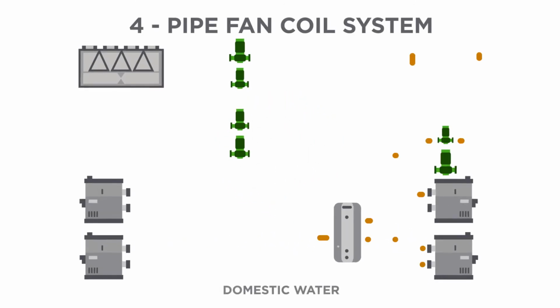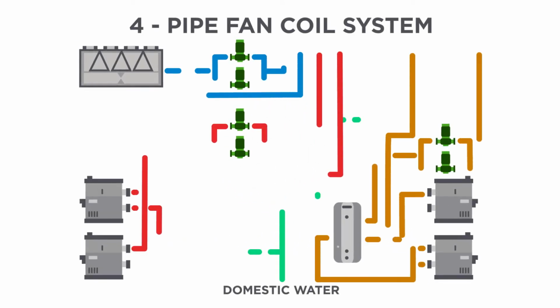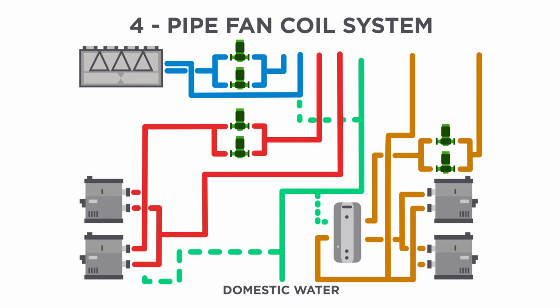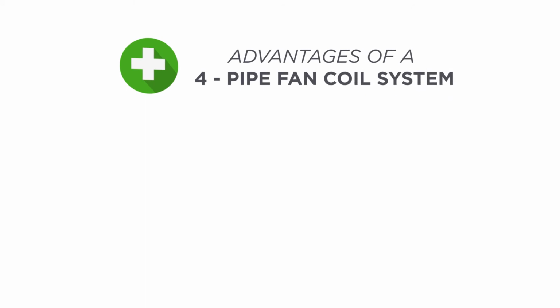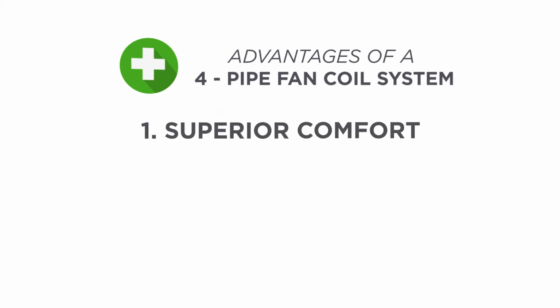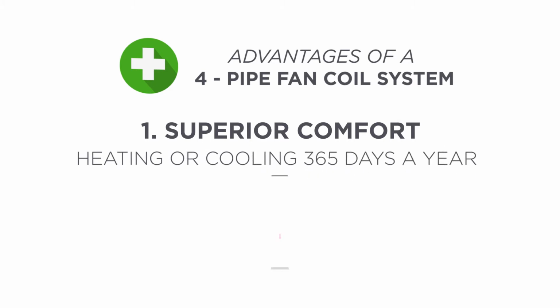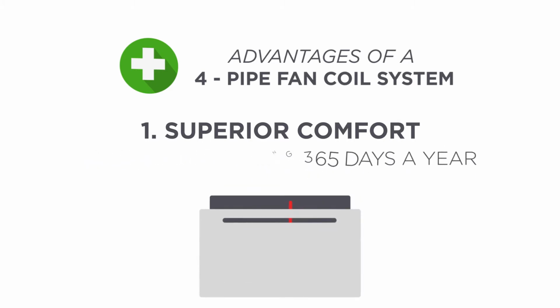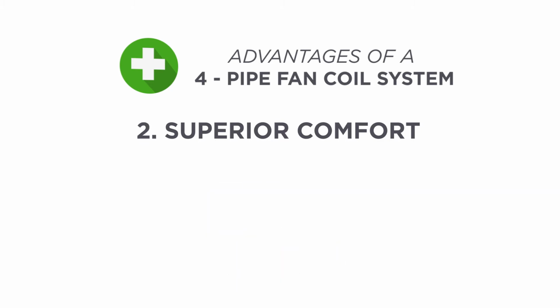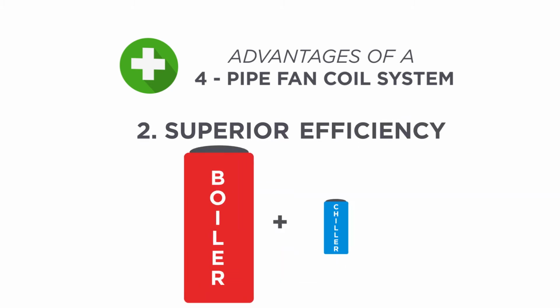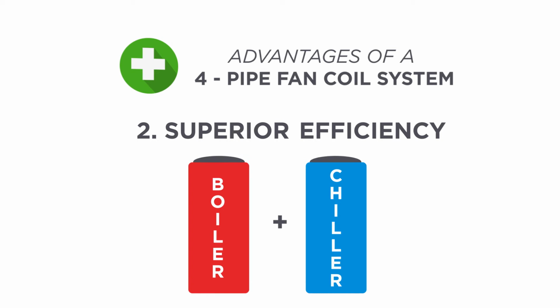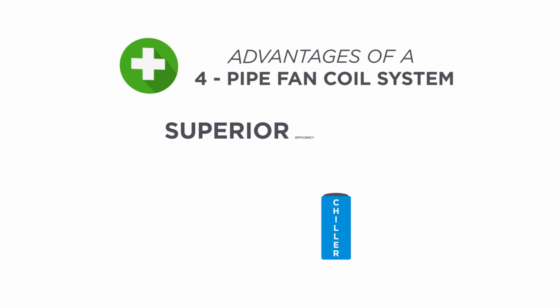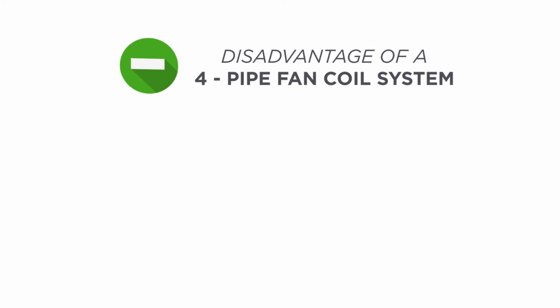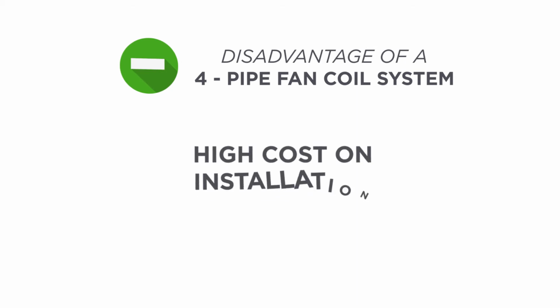This schematic shows a 4-pipe fan coil system, probably the most sought-after system today if the budget will allow. The advantages of a 4-pipe fan coil system are: number 1, superior comfort, because the tenant can have either heating or cooling 365 days a year, selectable from the thermostat in the space. Number 2, superior efficiency, because it has a central boiler and chiller that can be selected to be as efficient as the budget will allow. The main disadvantage of a 4-pipe fan coil system is high cost of installation.